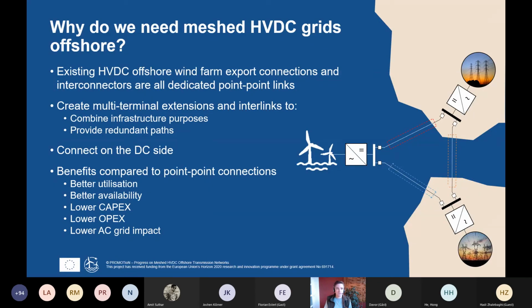To build the HVDC nodes offshore, gas-insulated substation equipment is necessary, which, by being 90% smaller than the air-insulated substation equipment, greatly reduces the cost of offshore platforms. Currently, the SF6 gas, which is used, has a strong greenhouse potential. So alternatives for this must be developed for use in future HVDC grids. And of course, we will hear more about this today.